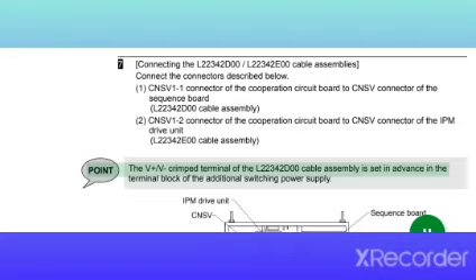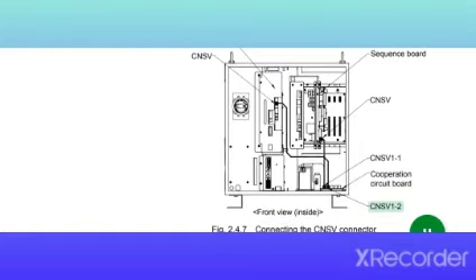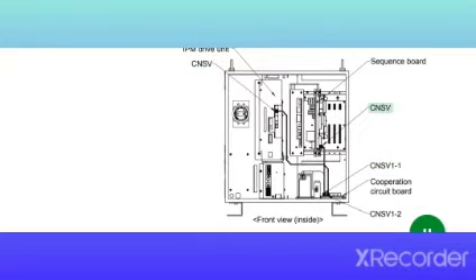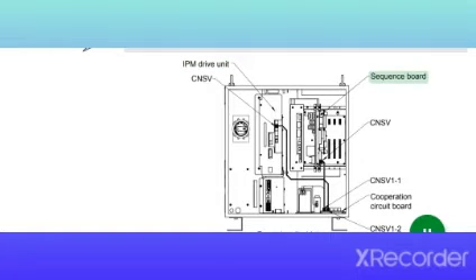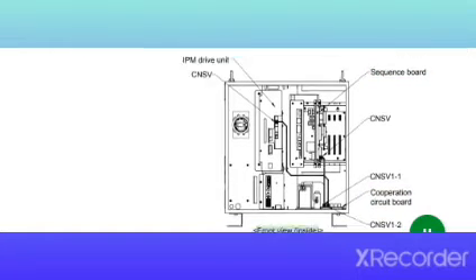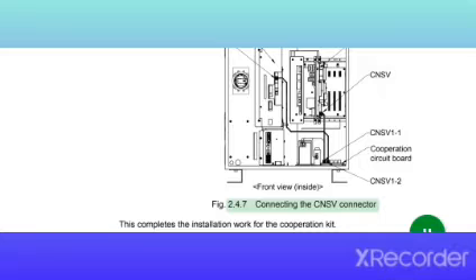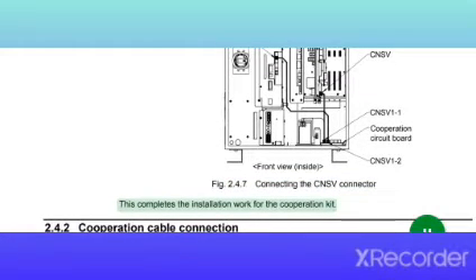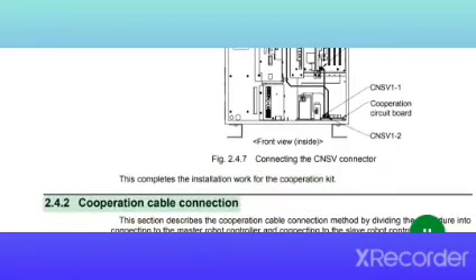The V+/V- crimped terminal of the L22342D00 cable assembly is set in advance in the terminal block of the additional switching power supply. CNSV1-2, CNSV1-1, CNSV, CNSV, IPM drive unit, sequence board, cooperation circuit board, front view inside, Fig. 2.4.7 Connecting the CNSV connector. This completes the installation work for the cooperation kit.